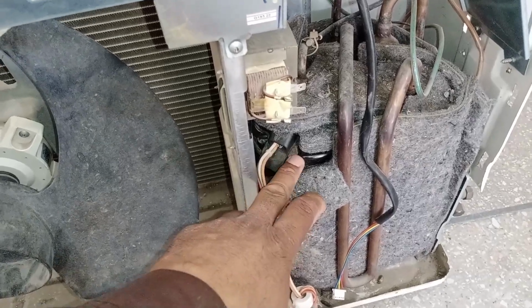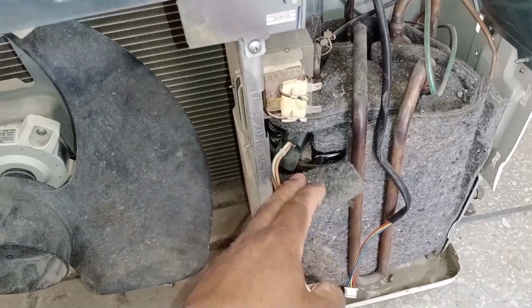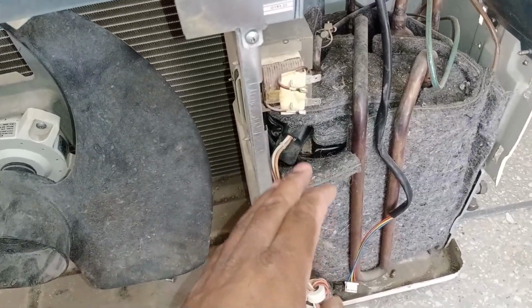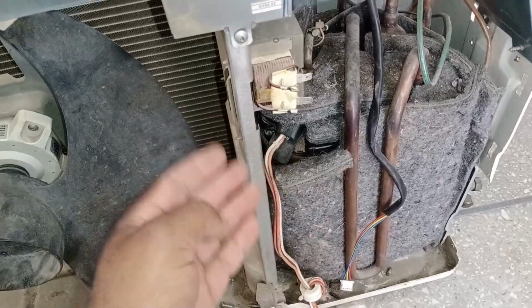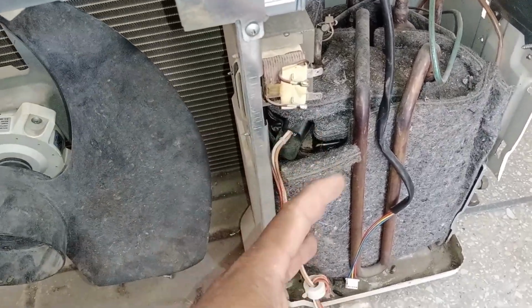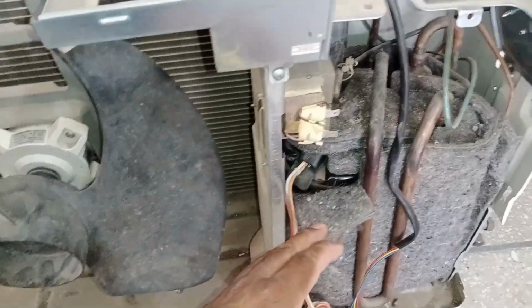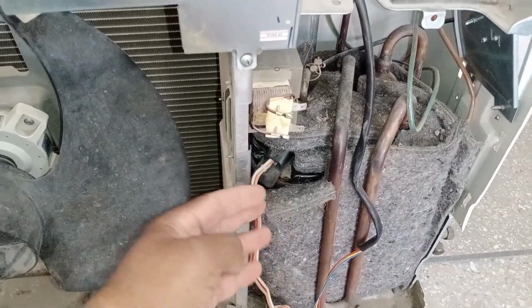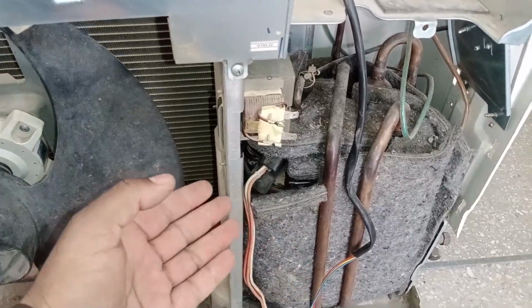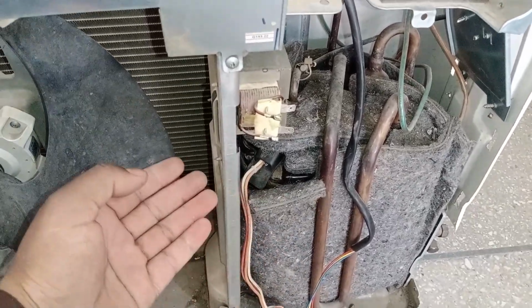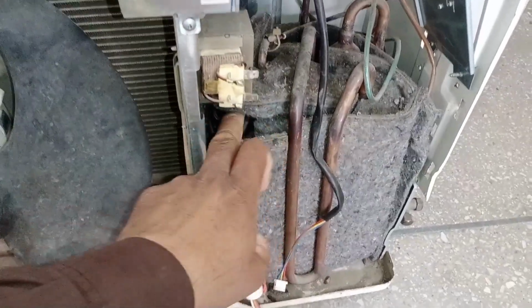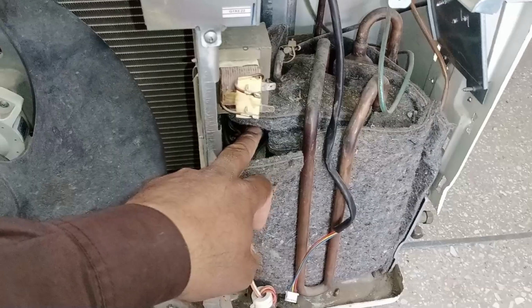Here's how compressor faults can manifest. Mechanically, if the compressor is jammed, this issue will arise. Electrically, a fault in the compressor can also lead to the same problem. The specific fault here is called abnormal compressor rotation, which means the PCB is unable to detect the compressor's rotation properly. In this case, the PCB interprets it as an abnormal rotation and registers it as a fault. Even if you correctly connect the PCB but fail to properly connect the compressor, this issue will persist.